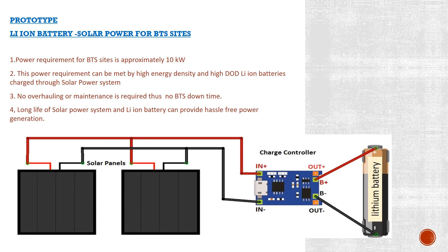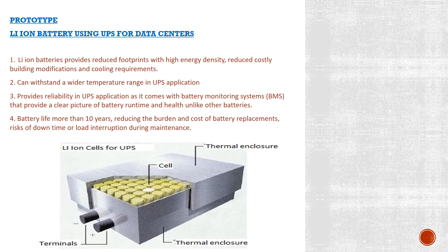This is a prototype of lithium ion batteries used for UPS in data center applications. Lithium ion batteries have a very reduced footprint, which entirely reduces building modification and cooling requirement costs for UPS placement. They can also withstand wider temperature ranges, an important feature for UPS applications, and support battery monitoring systems, which lead acid batteries lack. Battery life exceeds 10 years, reducing the burden and cost of replacements.